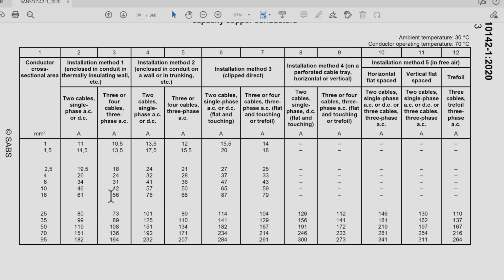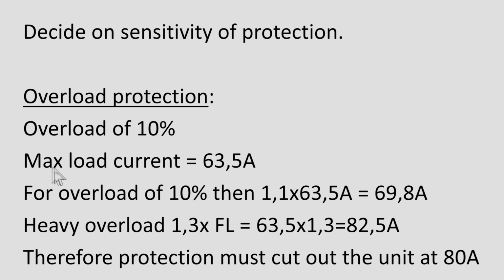Right, so let's look at the current carrying capacity that I need. According to my calculation, maximum load current is 63.5 amps. Now, it's always best practice to specify your cable a bit higher than that. Let's specify it for the overload condition. So that takes it to 70 amps. So that would be the minimum that I would specify this cable. So 70 amps is the minimum. You could, if you wanted to, specify your cable for the 82 amps or 130% full load, but it's unlikely that the inverter will ever work at that current rating. So it might be a bit of an overkill there. The minimum I would say is 65 amps, but I would prefer to go closer to 70 amps.